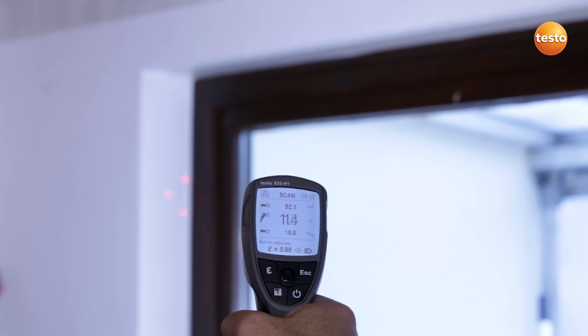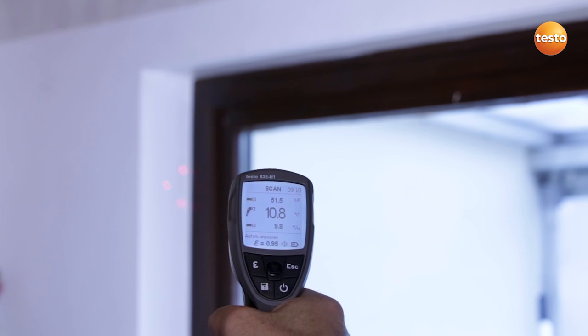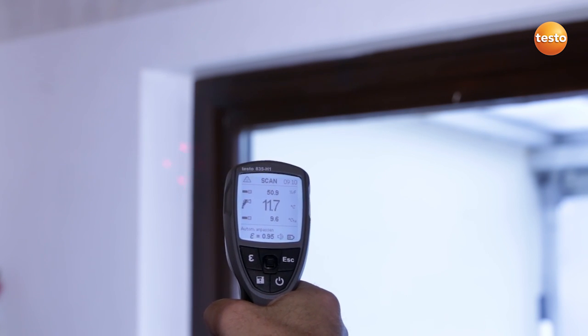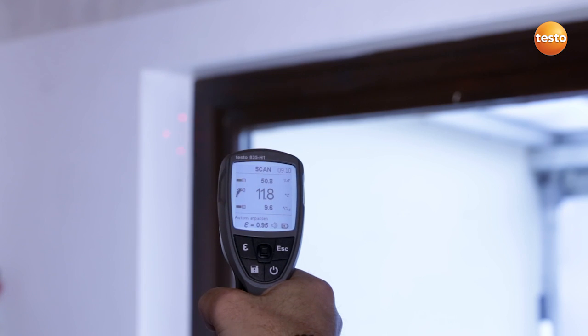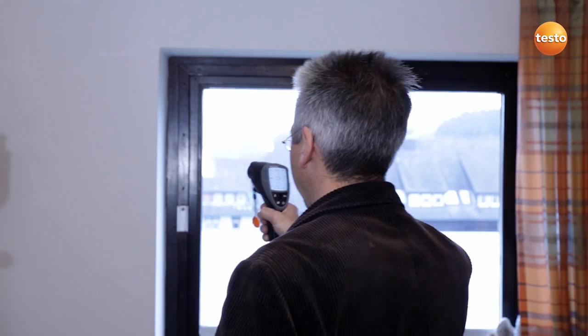The temperature drops off here, and at the top we have a roller blind casing which is open to the air and is insufficiently insulated. I've now checked all the main components. To be able to make a meaningful statement on ventilation behavior, we would need to use a Testo data logger. We're now going to go over to the neighboring apartment and check the temperature and moisture of the renovated parts and see what it looks like over there.